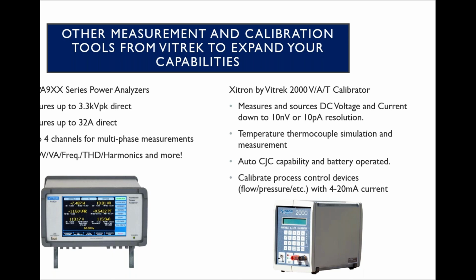We also have the Xitron by Vitrek 2000, which is a voltage, amperage, and temperature calibrator. It can measure and source DC voltage and current down to 10 nanovolt or 10 picoamp resolution. It has accuracies in the parts per million rather than the percent. It can perform temperature thermocouple simulation and measurement with an auto CJC capability, and it's lightweight, portable, and battery operated. It really lends itself to being a device that you can use anywhere in your lab or take out to the field.